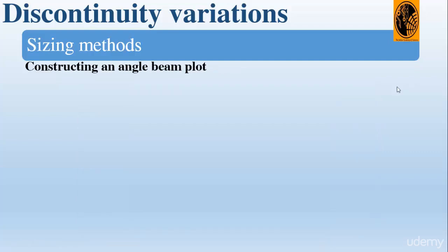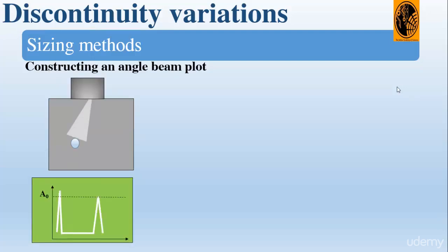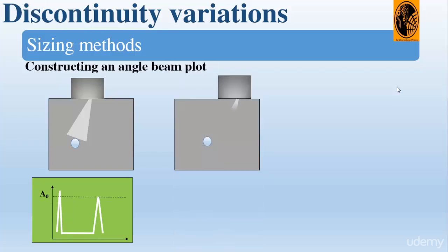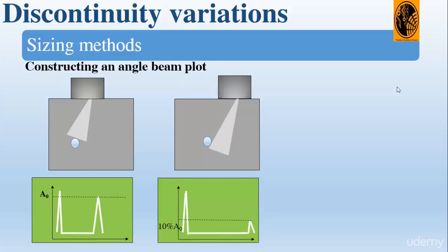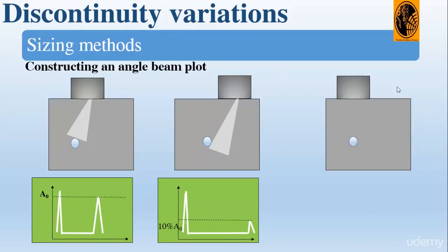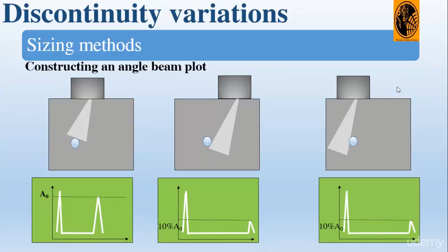For the construction of an angle beam plot, we follow the same steps. First, find the hole and get the maximum signal, then set it to full screen height using the gain function. Move the probe to one side of the block until we get 10% of the original amplitude, then do the same from the other side. We can use different depths as we did for the zero degree probe, and then use the same graph paper to construct the angle beam plot.